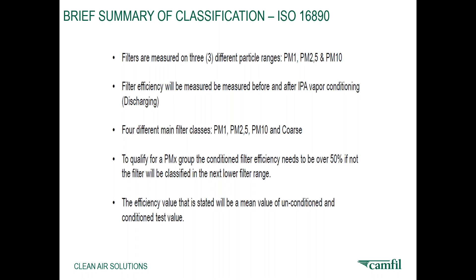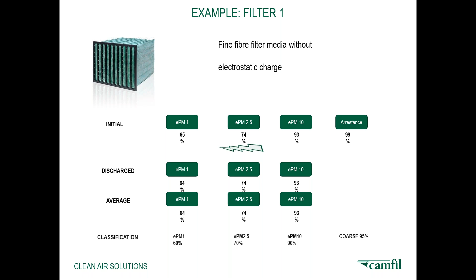I would like to explain this with an example. Suppose you have a fine filter without electrostatic charge, and it has been recorded for four readings. The initial ePM1 reading is 65%, 74% for ePM2.5, 93% for ePM10, and the arrestance is 99%. Now, if I discharge this filter, ePM1 would be 64%, ePM2.5 would be 74%, and ePM10 would be 93%. So the average comes to 64, 74, and 93.